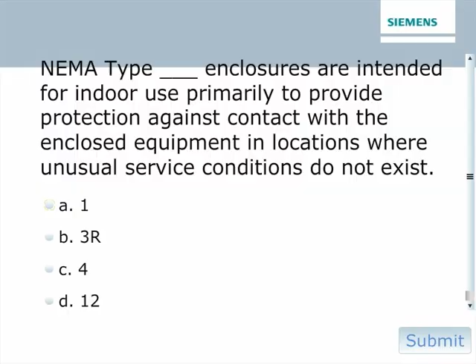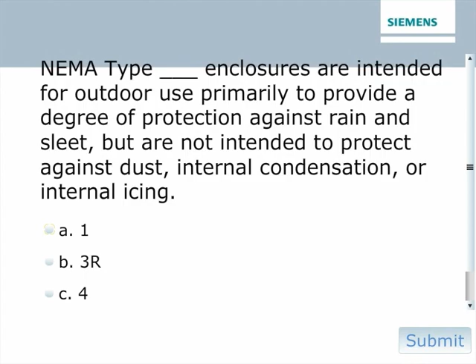Question 12. NEMA-type blank enclosures are intended for outdoor use, primarily to provide a degree of protection against rain and sleet, but are not intended to protect against dust, internal condensation, or internal icing. Is it A, 1, B, 3R, C, 4, or D, 12?